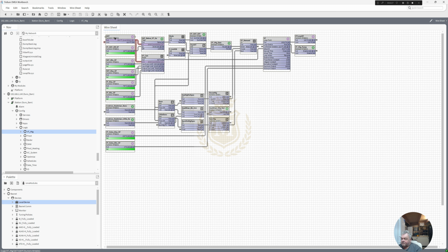And if I put this back down to 0 degrees outside, we have got the 75 degrees. So that's, I think, using the reset block.